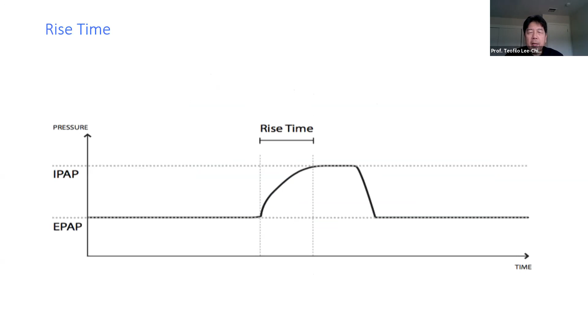You then have the rise time between 1 to 6. Rise time is the time it takes for the patient to go from EPAP to an IPAP. And there's a range from 1 to 5 to 6. So at 1, you see that the rise time is faster. And at 6, the rise time is slower. For most patients, a common default setting is a 3.